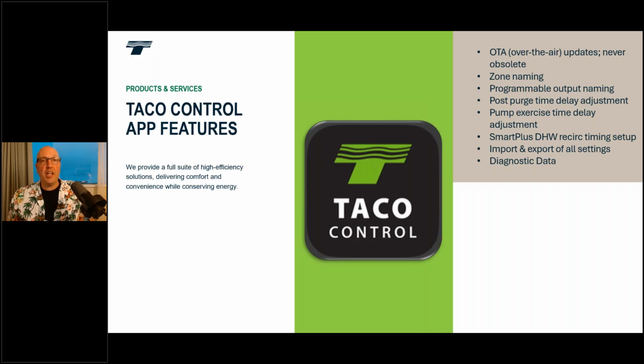Now we can do over the air updates, which means we can update the firmware as we come up with new software for these things or new things for it to do. But what can we do today with it? Well, you can name the zones. Now, remember, the app that we have for this is for you guys, our installer base out there. It's not a homeowner needed app. It's nothing that they're going to need to take a look at and change or use on a daily basis. It's just tying in and setting up for the first time. So you can name the zones. So you can name zone 1 DHW, zone 2 first floor, zone 3 Moe, Larry, Curly, whatever you want to. All right.